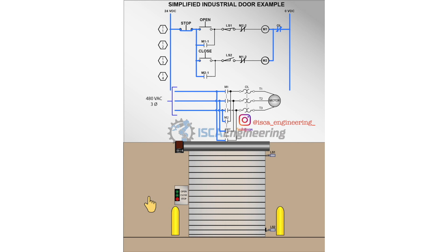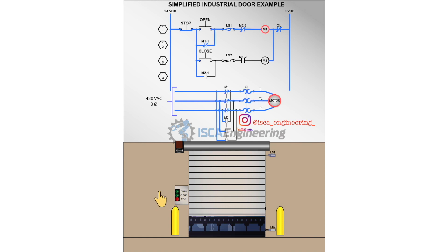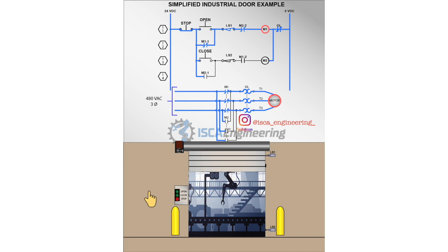Whenever the door is closed and limit switch 2 is actuated, then pressing the close button will have no effect on the door. To raise the door, you would press the open button to energize motor starter 1 and therefore turn the motor on. Whenever the door has reached its limit and actuated limit switch 1, then the limit switch's contacts will switch states and stop the flow of current to the motor.